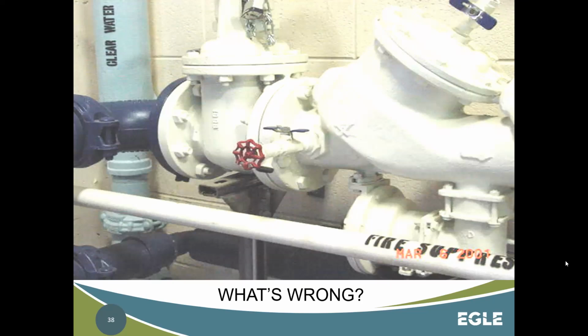The reason that's a problem is now if someone is using it like a hose bib and connecting to it, we are basically introducing a new opportunity for a cross connection to occur. And now we've removed one of the test ports, so we can't be checking to see if this RPZ is functioning correctly. So again, these are the kind of things that you can catch, and why it's important to physically get out there and look at some of these places.